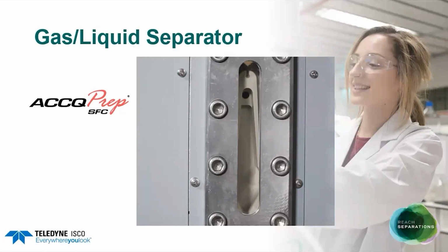One more thing to consider here is that there is a minimum co-solvent flow requirement for any GLS to function effectively, and it's around about 10 mils a minute in this case. So depending on your purification conditions, there is a potential to be below this value. A feature on the AccQPrep SFC is on top of the two main mobile phase pumps in the system, there's a third makeup pump built into the system that feeds directly into the mobile phase stream prior to the GLS. This makeup pump is activated automatically when the system calculates that the solvent flow is too low, and this requires no extra intervention from the user.